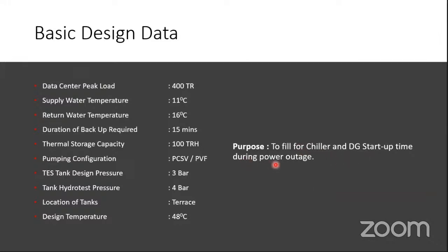This essentially means that whenever there is a power outage, the cooling in a data center is very crucial. Even for 5 minutes, no chill water supply could be fatal for a data center. So for that reason, to fill for that period when the DG is also starting and the chiller is also ramping up to its full capacity, for this time duration, a backup chill water supply is planned.